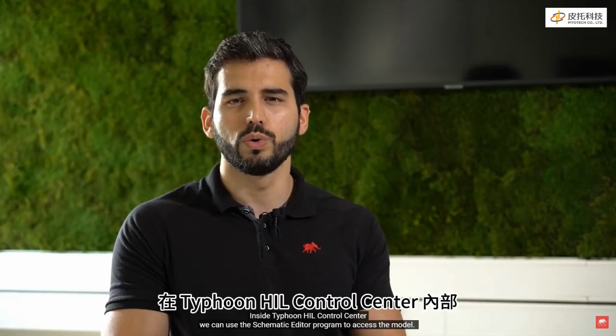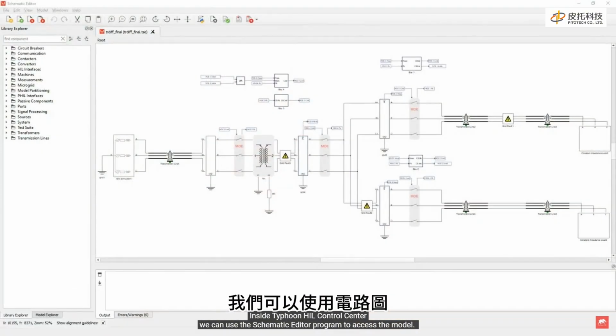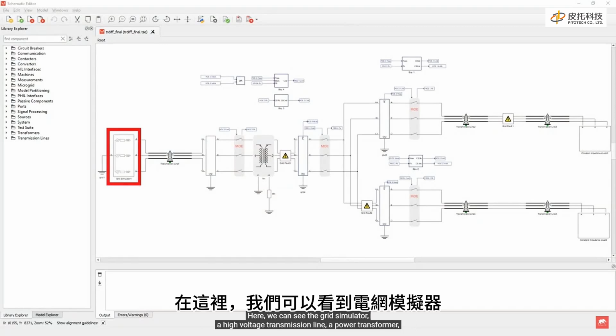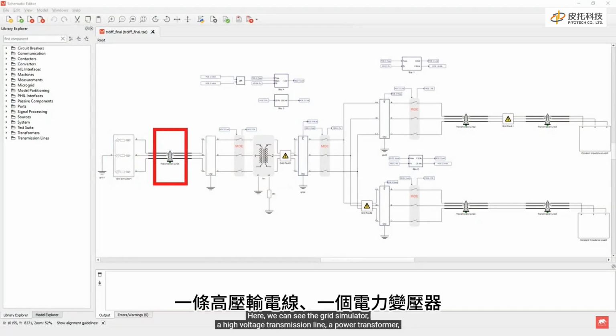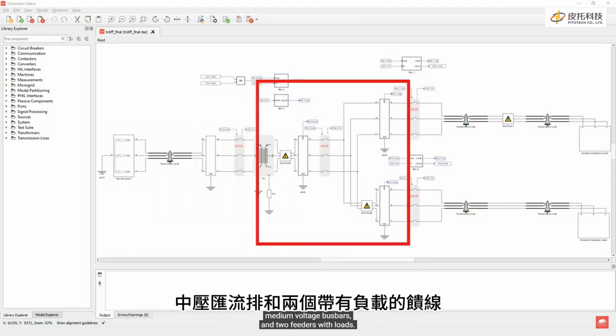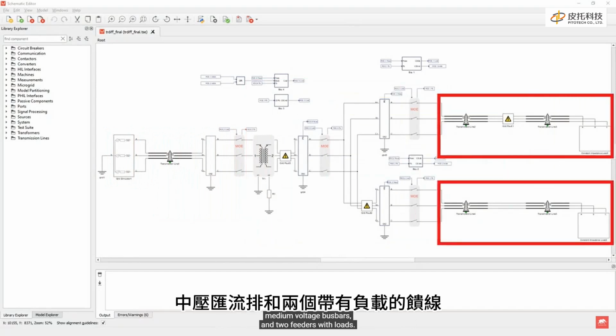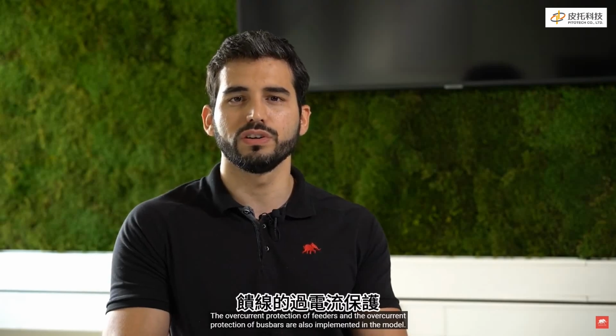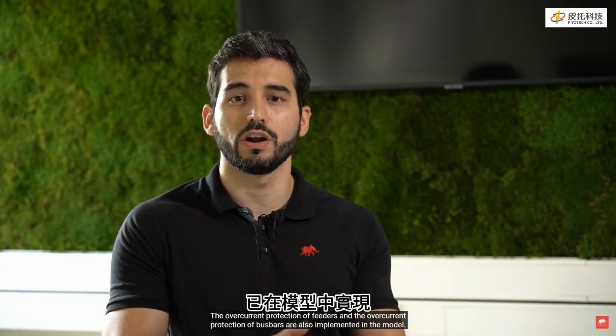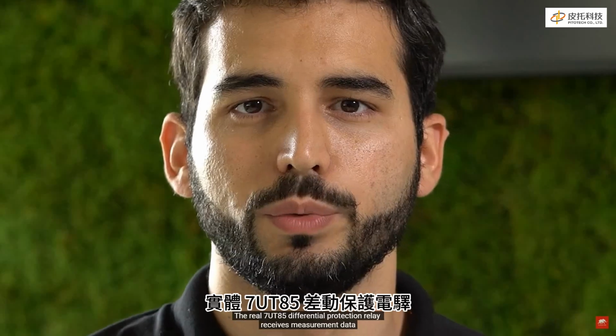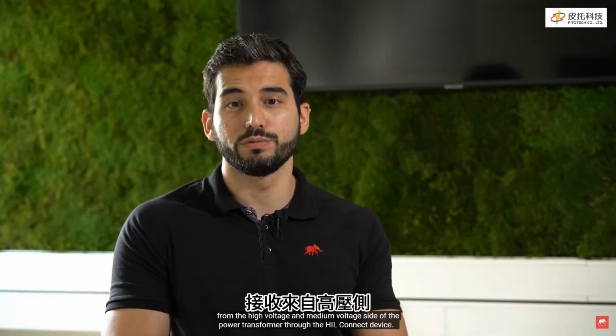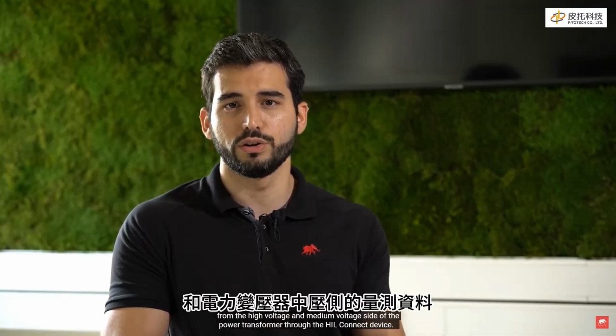Inside of Typhoon HIL Control Center, we can use the schematic editor program to access the model. Here we can see the grid simulator, a high voltage transmission line, a power transformer, medium voltage bus bars, and 2 feeders with loads. The overcurrent protection of feeders and the overcurrent protection of bus bars are also implemented in the model. The real 7UT85 differential protection relay receives measurement data from the high voltage and medium voltage side of the power transformer through the HIL Connect device.